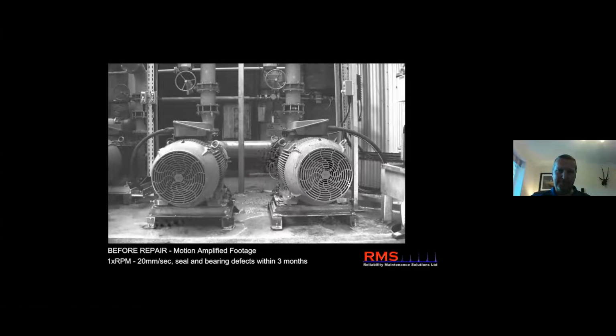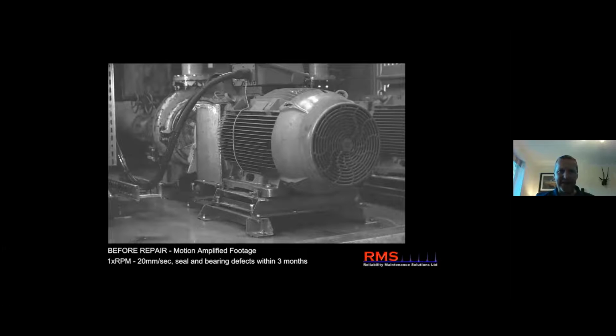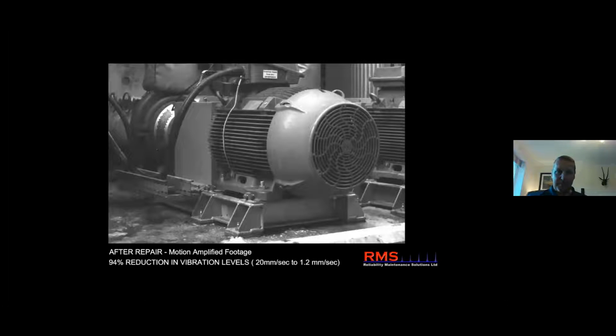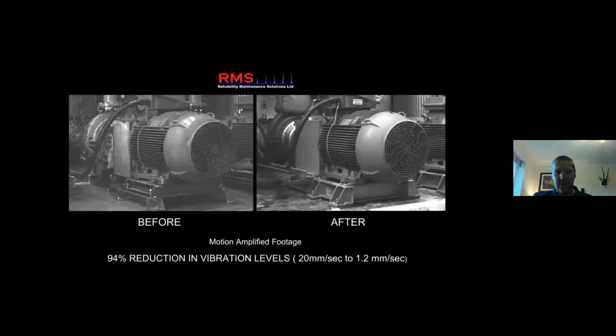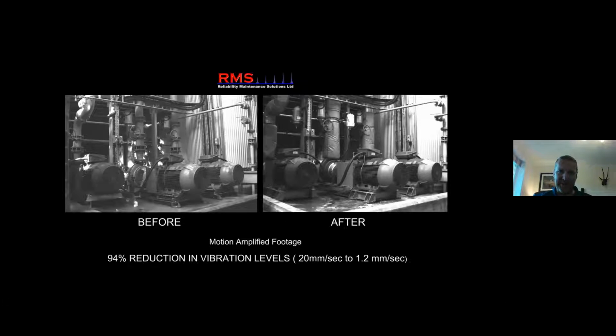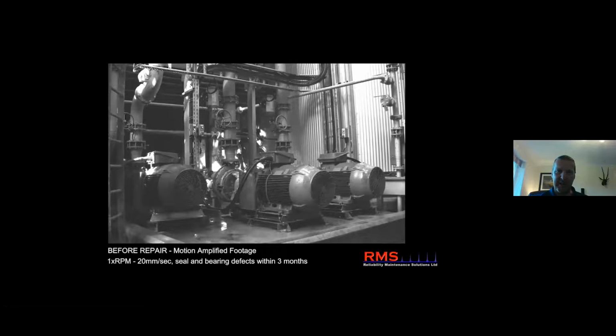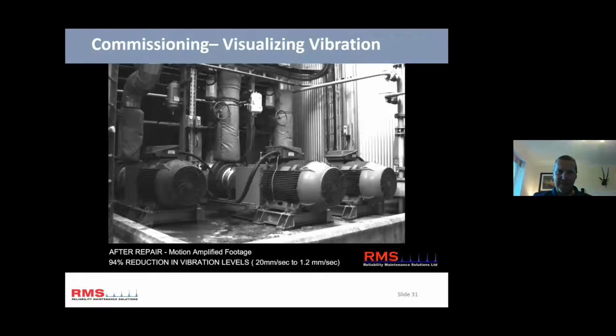You can see serious base movement, loose bolts, twisting — I think they were getting bearing defects very quickly on this. Really poor installation. The project team was brought in to get these pump bases sorted, and here's the before and after, with the right-hand image motion amplified. This is the beauty of the technology — it's very difficult to make a good machine look bad with it. That shot is amplified, but the vibration levels are so low it's not showing any motion, and that's one of the successes with this technology.